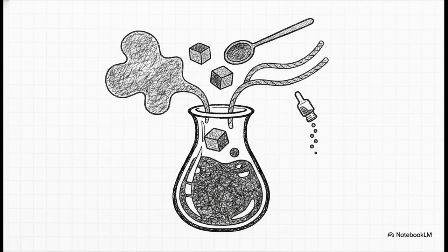Yeah, it has the base resin, but it's also packed with plasticizers for flexibility, stabilizers to survive the heat of processing, crosslinkers, and even blue colorant master batches. And those colorants, they bring their own carrier resins and impurities along for the ride. Every single one of these additives is a potential migrating chemical species that your patient could be exposed to.